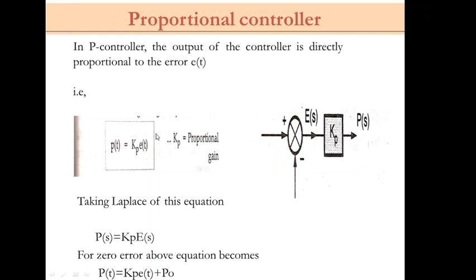So then moving further, the proportional controller depends on the proper design of gain Kp for a fixed P0, where P0 is nothing but the controller output with zero error. For a fixed P0, if the gain Kp is high, then a large output results for a small error, but only a narrow error band can be handled. Beyond these limits of the error, the output will be saturated. If the gain is small, then the response is smaller, but a large error band can be handled.